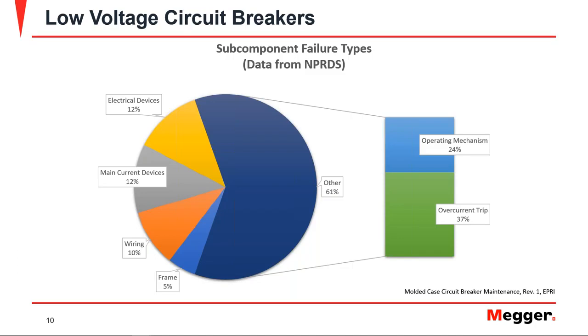The graph that you're looking at right now is from the nuclear industry. It was published by EPRI. And even though it is from the nuclear industry, it's a good representation that gives a very good indication of where the majority of failures happen on low voltage circuit breakers, which you can see is the operating mechanisms as well as the overcurrent trip elements of the breaker. So it's really important that we make sure not only that the circuit breaker is in good condition, but also that the settings, in case we can change those in the breaker we're testing, are programmed correctly.